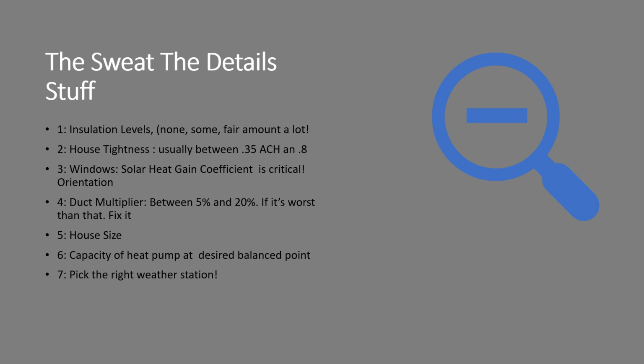House tightness, this is another error we see a lot. ACH, the leakage rate of the house, air changes per hour, is usually between 0.35 and 0.8. It's never 2. I have seen heat loss and heat gain calculations at 2. That's a barn with the door open on a windy day. Window solar heat gain coefficient is critical. You can usually find that, generally in the Northwest, it marches right along with the U value. So if you have a 0.35 U value window, chances are the solar heat gain coefficient is very similar. Orientation is critical. Windows that face east and west get most of the summer sun. It's low in the sky and it can just beat through. So make sure you have the windows in the house pointed the right direction.